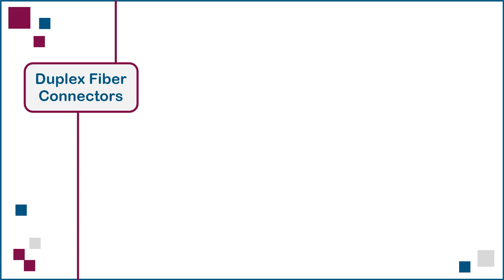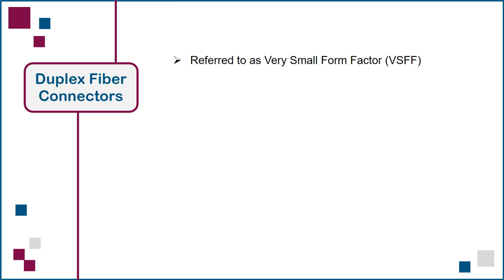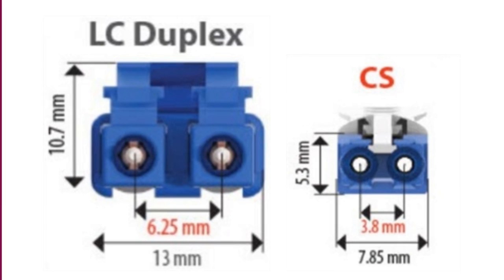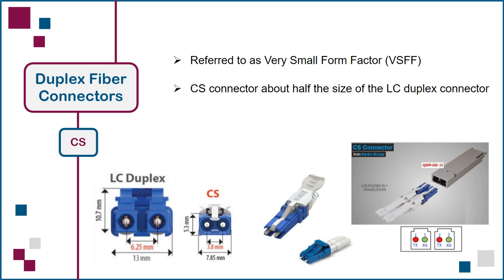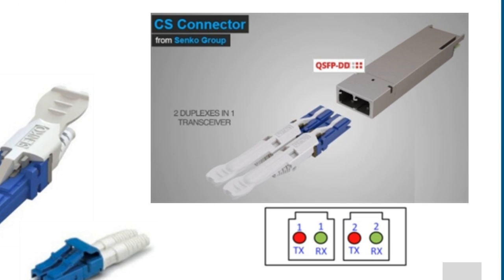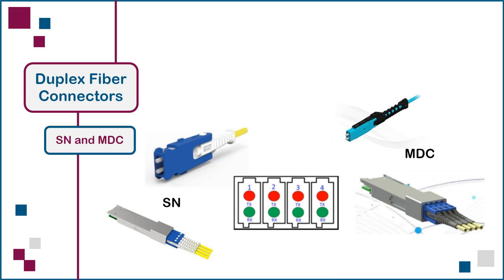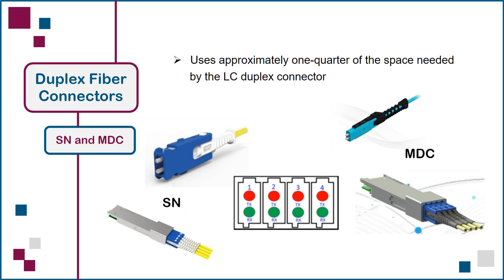Three new duplex connectors have been introduced as the next generation, referred to as very small form factor, or VSFF connectors, to differentiate them from the small form factor LC. The CS connector takes up approximately half the space of the LC duplex, making it possible to insert two duplex CS connectors, or four fiber strands, into a patch panel adapter or optical transceiver that is the same size as a two fiber strand LC duplex transceiver, as shown here. The SN and MDC connectors are even smaller, taking up approximately one quarter of the space needed by the LC duplex, making it possible to insert four duplex SN or MDC connectors, or eight fiber strands, into a patch panel adapter or optical transceiver that is the same size as an LC duplex transceiver, as shown here.